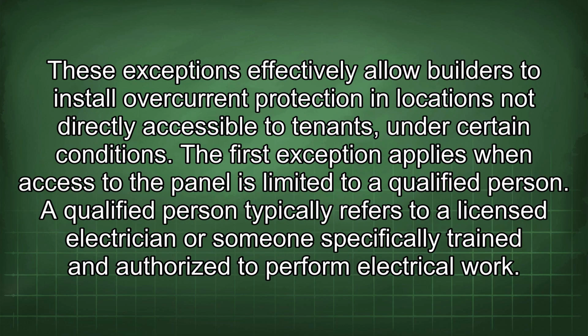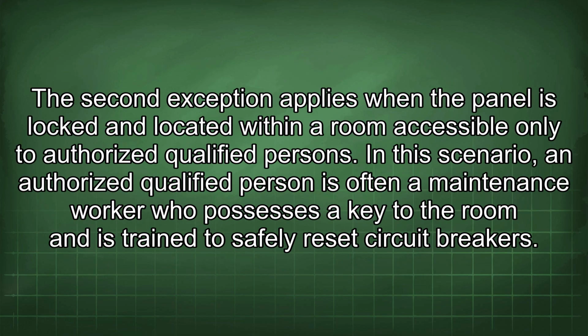These exceptions effectively allow builders to install overcurrent protection in locations not directly accessible to tenants under certain conditions. The first exception applies when access to the panel is limited to a qualified person. A qualified person typically refers to a licensed electrician or someone specifically trained and authorized to perform electrical work. The second exception applies when the panel is locked and located within a room accessible only to authorized qualified persons. In this scenario, an authorized qualified person is often a maintenance worker who possesses a key to the room and is trained to safely reset circuit breakers.